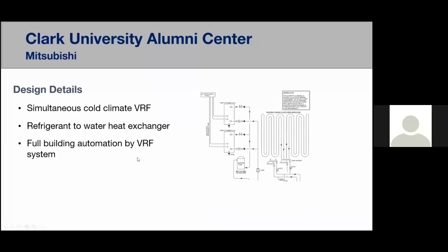So looking at this design, we did want simultaneous heating and cooling. It was a perfect application, with a lot of unique zones that could use heat recovery to its advantage, as well as using cooling or heating in certain spaces. Cold climate: Worcester's winter design temperature is around 0 or 2 degrees, according to ASHRAE. So we had to make sure we were going to get the heating capacity that we need, which resulted in low ambient condensers. Then we also had a little challenge with using a refrigerant to water heat exchanger.